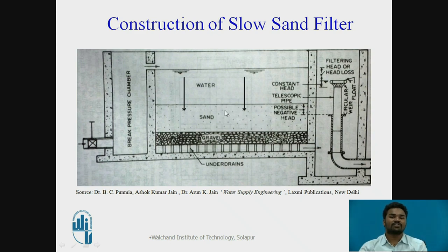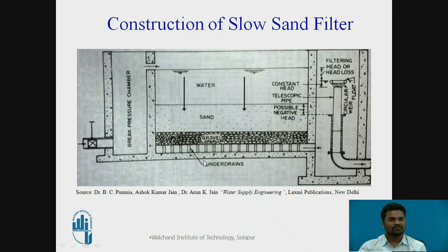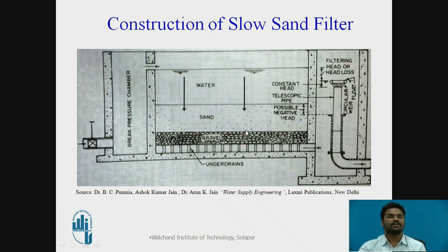The slow sand filter is a rectangular basin, open and constructed below the finished ground level. The surface area of the slow sand filter is between 500 to 2000 m². The slope of the floor is 1 in 200. The rate of filtration is about 100 to 200 liters per m² per hour. The depth of the tank is 2.5 to 4 meters.